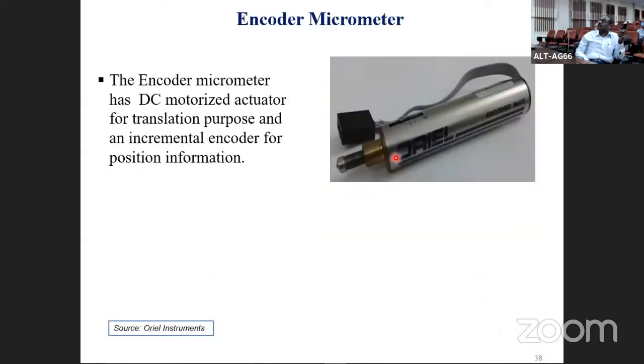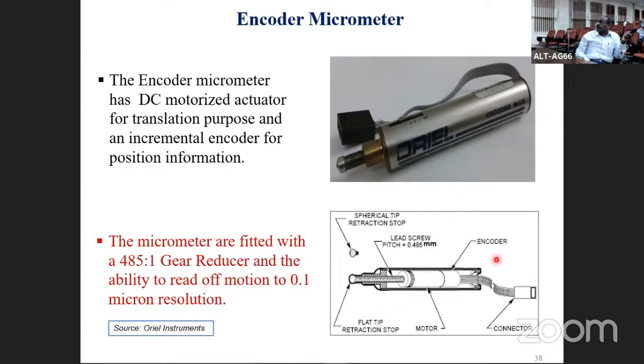So before that, I will just give a quick information about this encoder micrometer. It has a DC motorized actuator for translation purpose, and an incremental encoder for position information. The key to that is it has a very fine pitch screw which moves into a threaded portion, and with a gear ratio of 485:1.